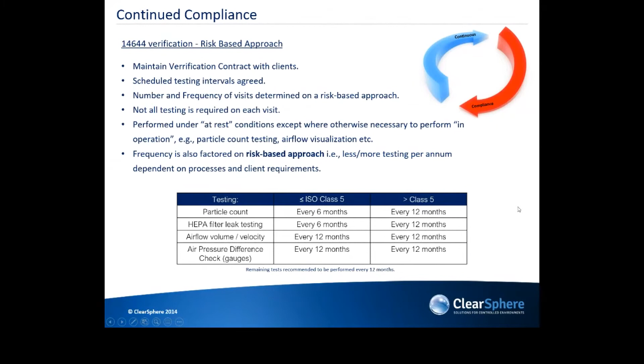From a continued compliance point of view, it's the ISO 14644 verification risk-based approach. From a maintenance verification standpoint, we contract with clients and agree schedule testing intervals, number and frequency of visits, as we would have done with St. Vincent's University Hospital. Not all testing is required at each visit - HEPA filter testing, depending on the classification of the room, is performed under at-rest conditions except where otherwise necessary in operation, for example particle counting, so there may be operators in there or there may not. The frequency is factored on a risk-based approach, based on the classifications.